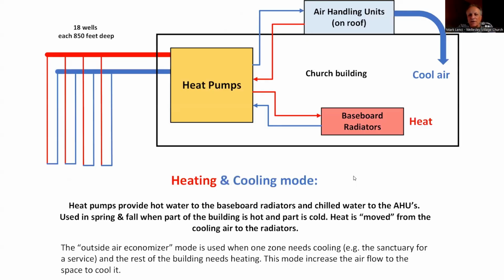Next slide. There's a mixed mode. This is where the north side of our building in the spring is cold because it's facing north, and the rooms on the south side of the building are sweltering because of the low angle sun coming in. Much of the heat that's removed from those hot rooms simply goes around and heats the cold rooms. There's no use sending that water back down the ground, cooling it and heating it back up again, right? So we actually move heat in these 2 modes, spring and fall, between one side of the building and the other. Another very cost-effective way.